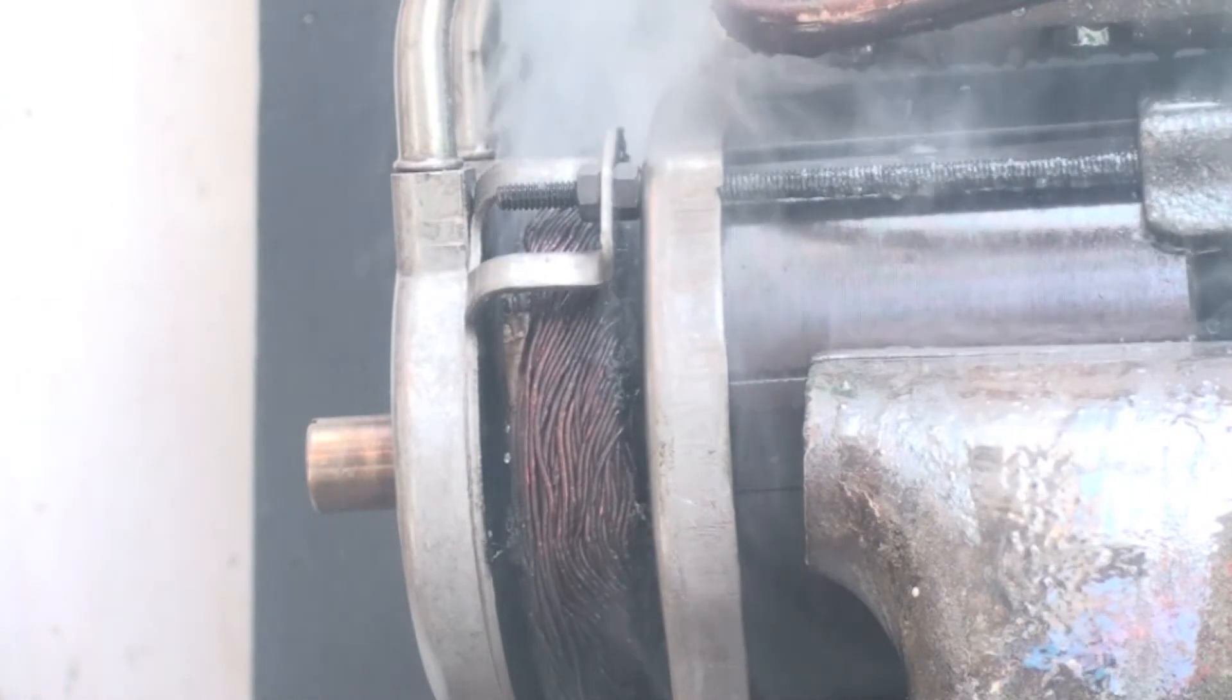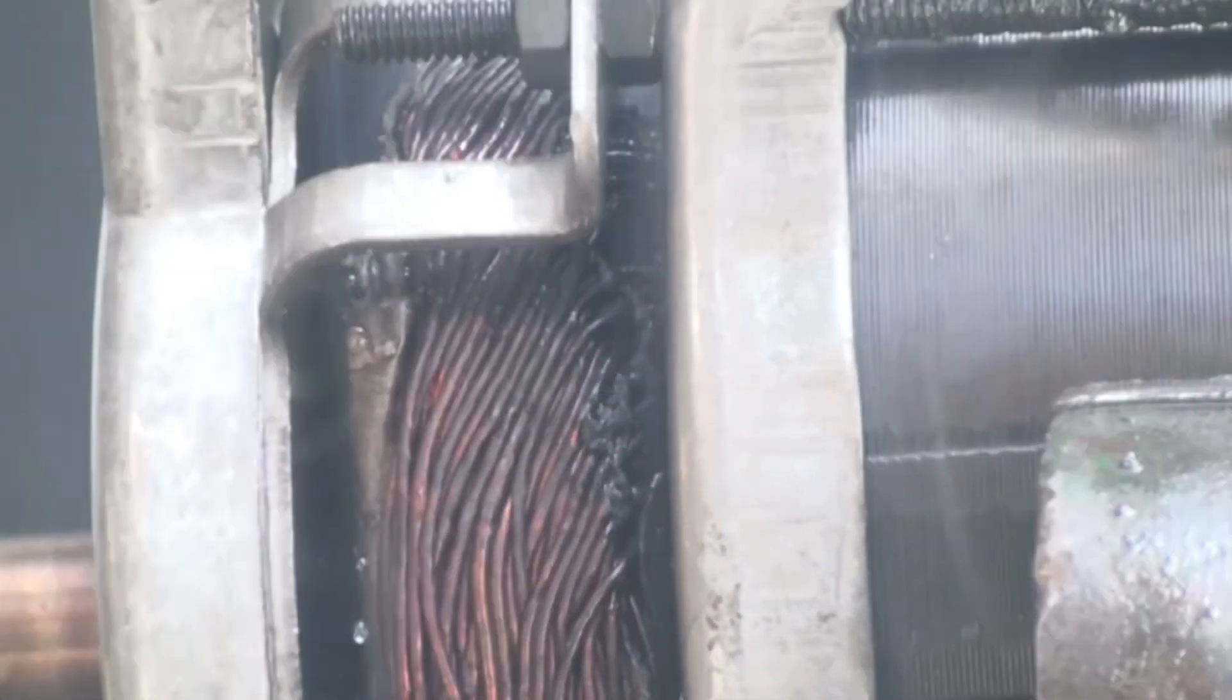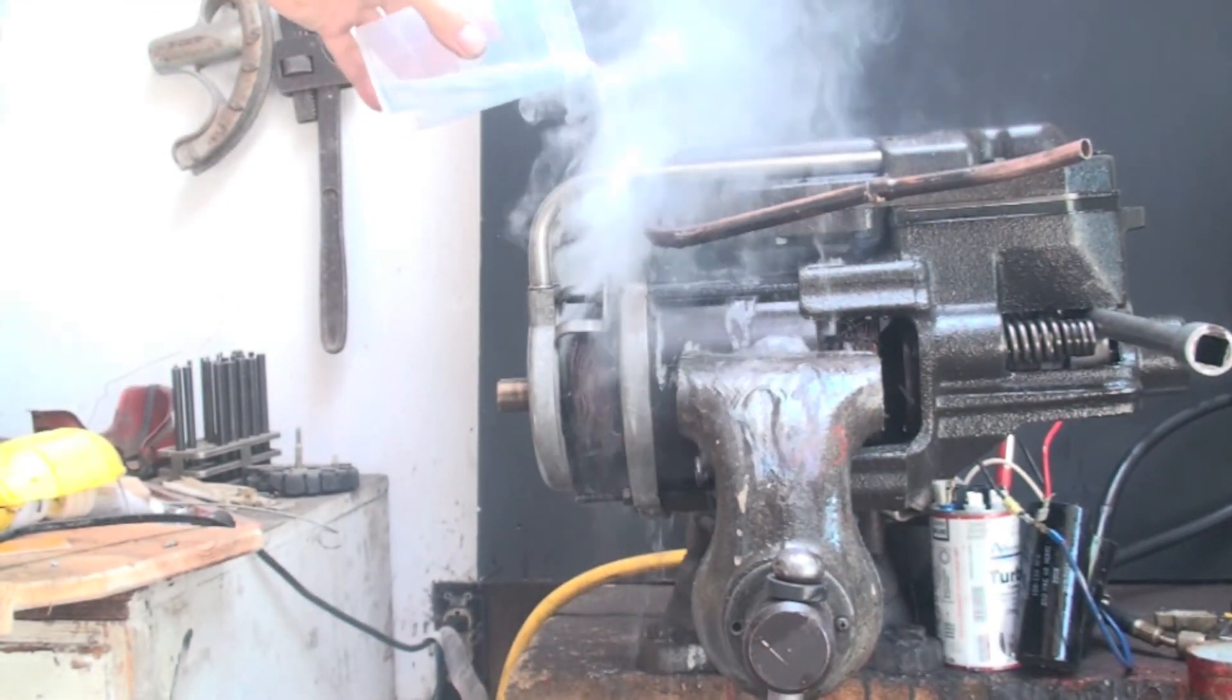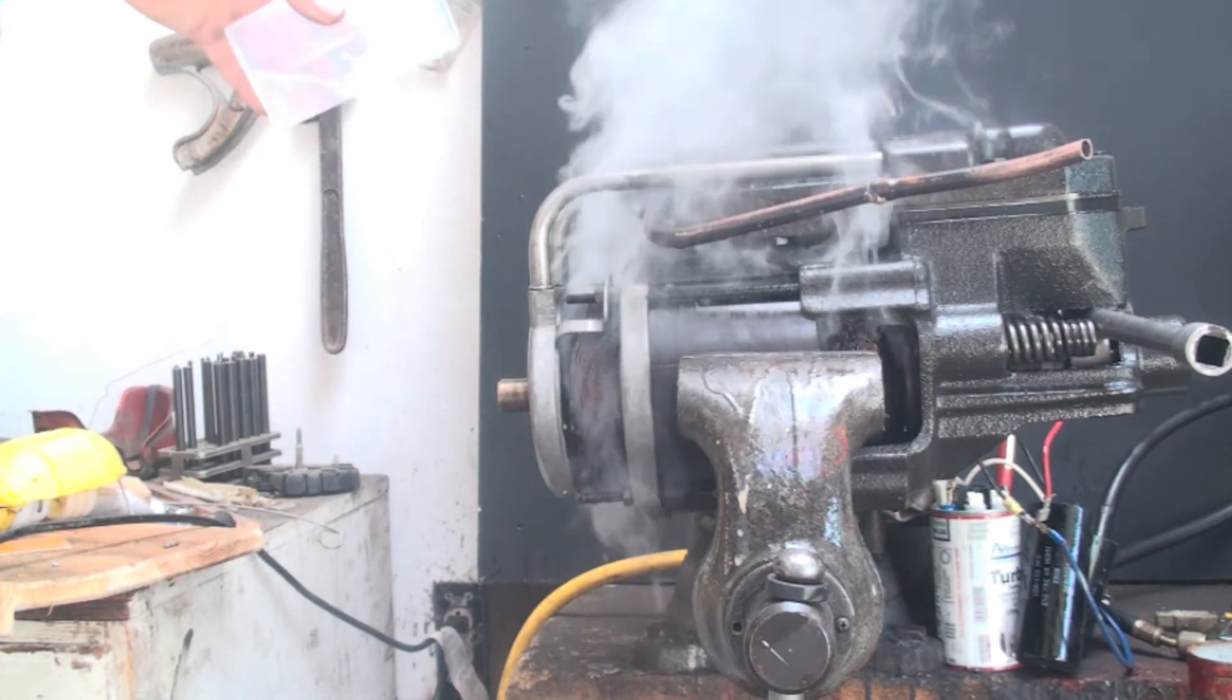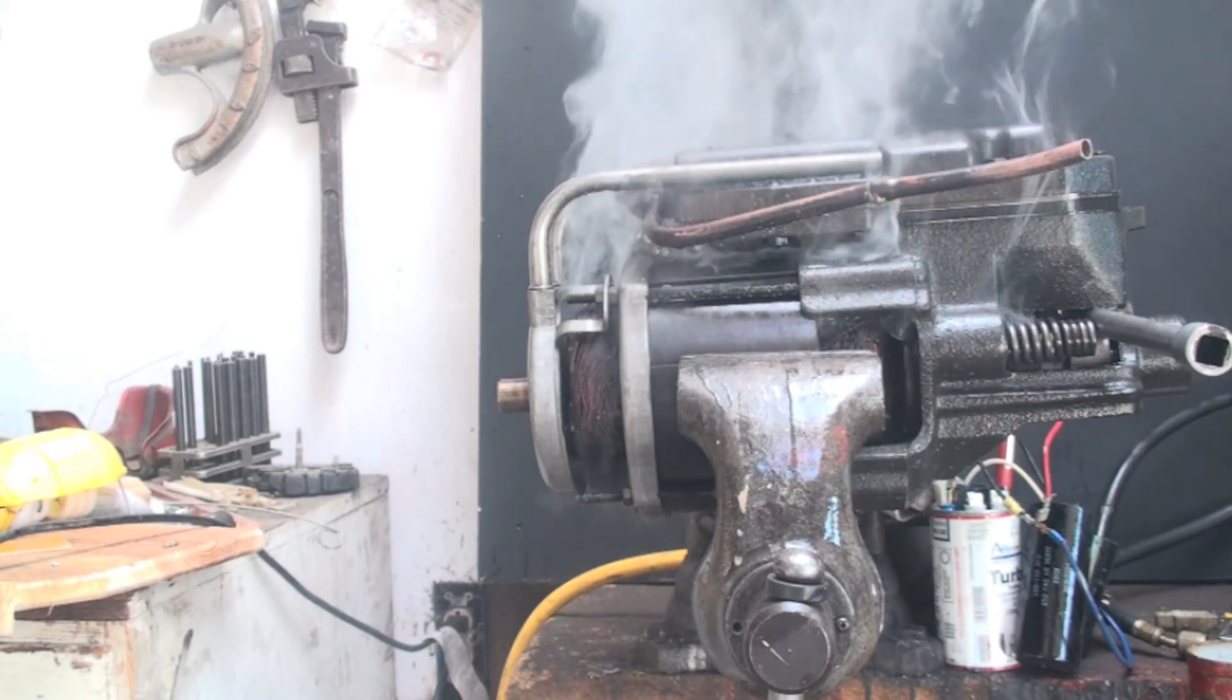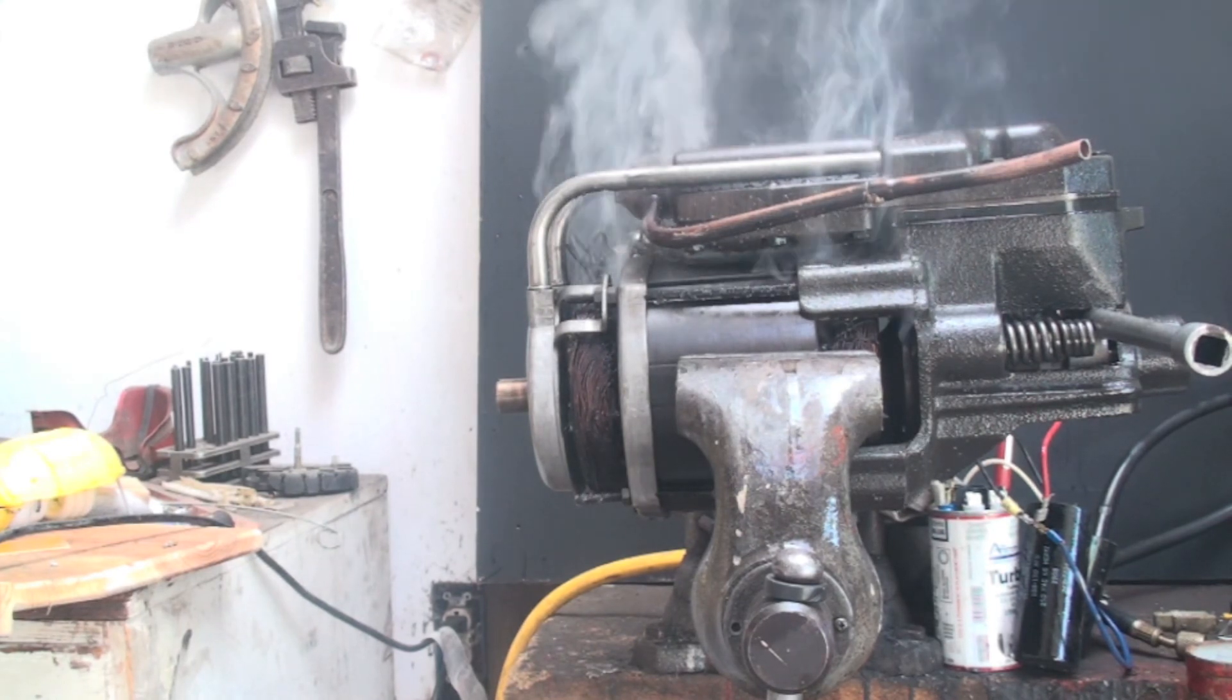This only kicked off the breaker once and took quite a while to kick off that internal overload. I did kind of fool it because I cooled it down too much. But these things should not be run under lock rotor conditions because they will fail, and this is a pretty good example of catastrophic failure.